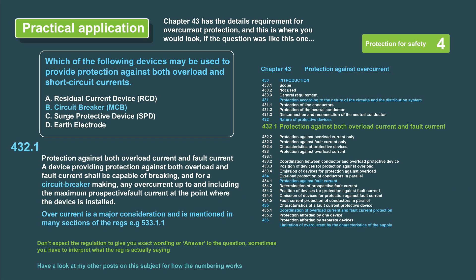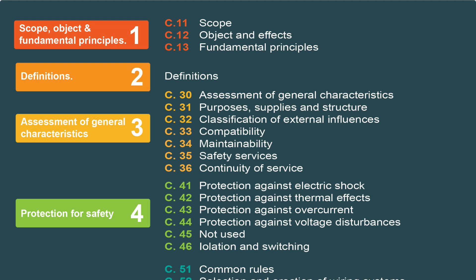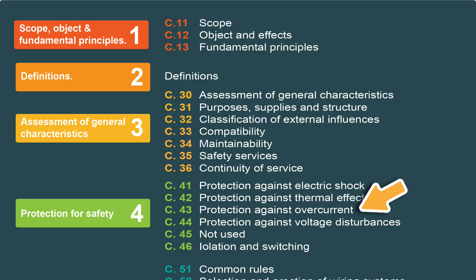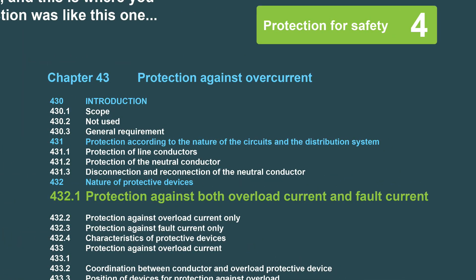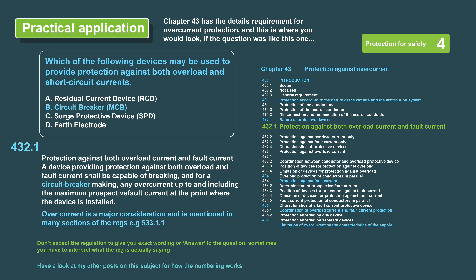Here's another question on overload current: which of the following devices may be used to provide protection against both overload and short circuit currents? It's not asking a fundamental principle — it's asking for a specific example. You should have a good idea of what the answer is, but you might just want to check. Start at the contents page: overload and short circuit currents, we'll be thinking about protection for safety, which is part four. Look through the contents and there it is — protection against overcurrents. In the section on nature of protective devices, regulation 432.1: protection against both overload currents and fault currents. A device providing protection against both overload and fault currents shall be capable of breaking — and for a circuit breaker, making any overcurrent. It's really quite simple to find the answers if you do it methodically.